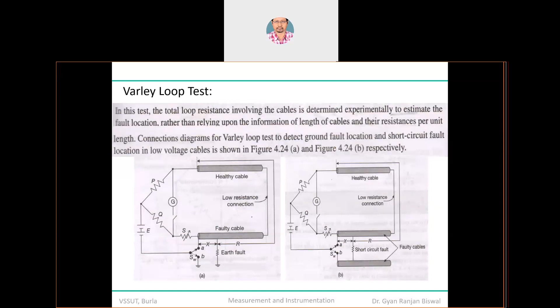Correction factor needs to be included, and you also have to count the temperature variation, because remember, if it is a conductor, it is definitely influenced by variation in temperature. So one question is given to you in a test to find the earth fault by the Murray loop test. The faulty cable has a length of 5.2 kilometer.